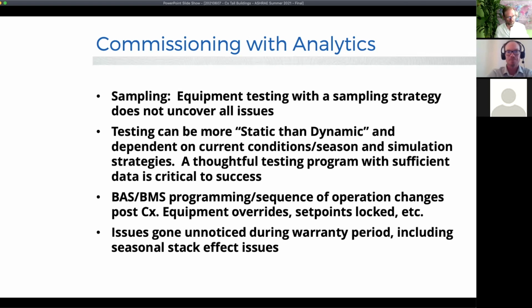Yeah, absolutely. A lot of times we get called back, and keeping your documentation is very important—the time, the dates, the information from your commissioning test—because we do get that critique a lot, and a lot of times it's just things have changed. Somebody might have changed it. Yesterday I went to a project that was actually a maintenance issue, but they thought it was a construction issue. It hadn't been maintained properly and it shut the system down, and it had nothing to do with how we did it—it just didn't get set up and maintained correctly after we commissioned the project.